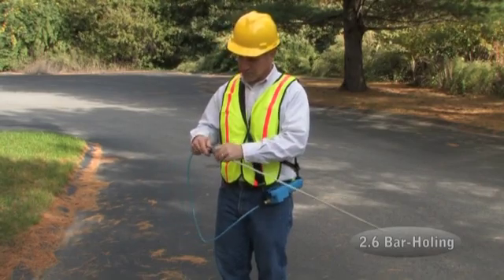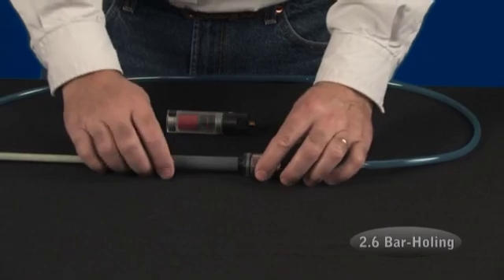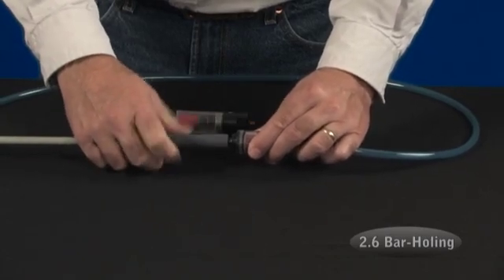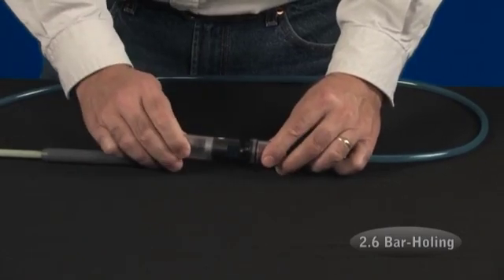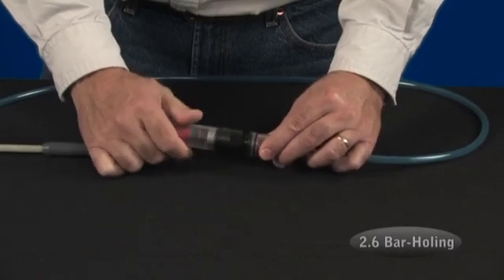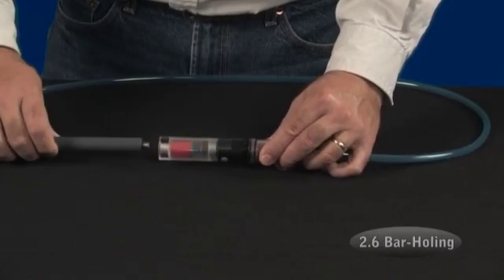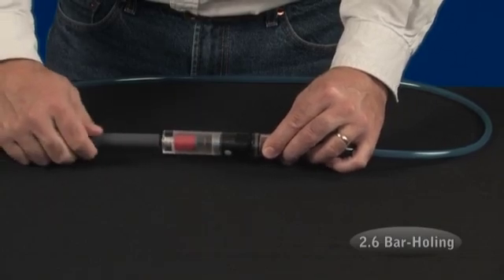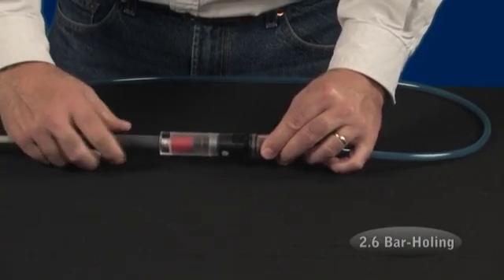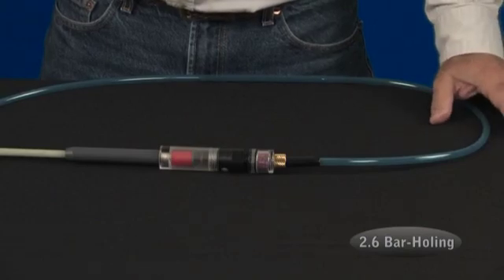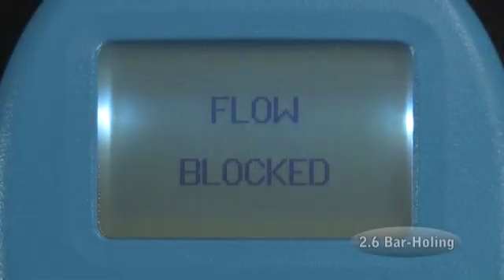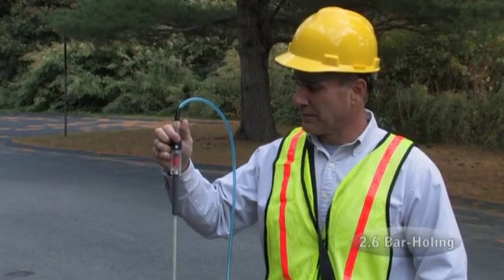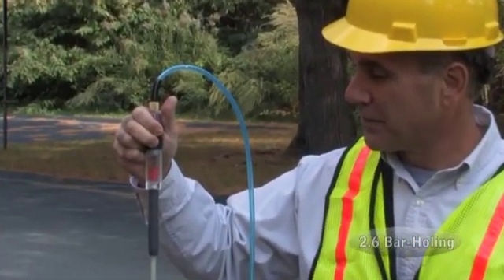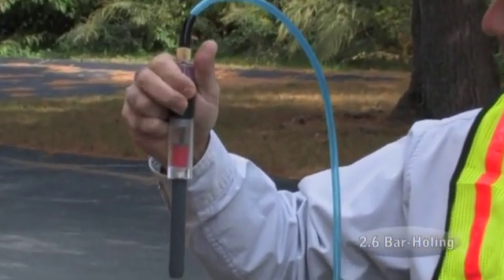If you expect to find water in your bar hole, it's best to use a water stopper. The water stopper should be attached between the primary filter and the bar hole probe. Any water coming up the probe will collect in the water stopper. When it fills with water, the internal float will cut off the flow so that no water can pass through to the detector. Again, you will see the words "flow blocked" on the screen. To clear the blockage, hold the bar hole probe vertically and press the white release button on the side of the water stopper.